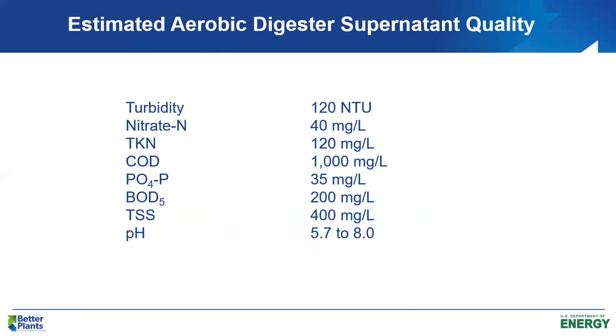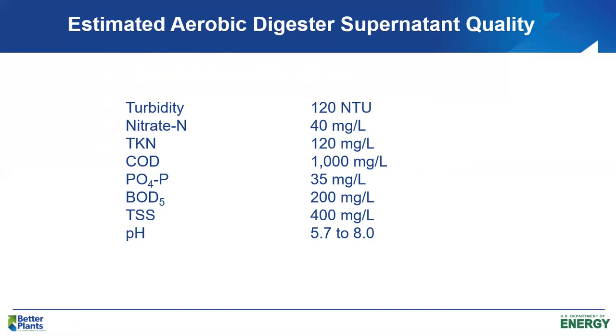Supernatant quality from an aerobic digester is generally better than from an anaerobic digester. Typical estimated values: approximately 40 mg/L nitrate-nitrogen, 120 mg/L TKN, 500–1,000 mg/L COD, 35 mg/L orthophosphorus, 100–200 mg/L BOD5, 300–400 mg/L suspended solids, and pH of 5.7–8.0. These values can vary, but this is typically what to expect. This waste stream is sent back to the head of the activated sludge process to be retreated.